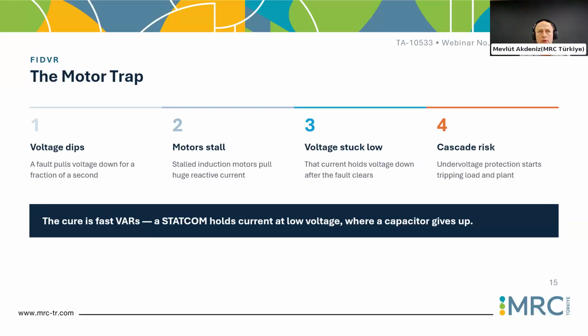And it is also related to the voltage strength of the grid at that point that I mentioned a couple of minutes ago. The voltage strength here is not only the short circuit power, but also the QV curve edge points. Because even if we have short circuit power here, maybe from huge power plants, if the short-time overloading of the reactive power of the system is not high enough, short circuit power alone does not guarantee recovery from such dynamic or slow voltage recovery issues in the grid. So we need both short circuit power strength and fast reactive reserve at these problematic areas dominated by motor load and connected to long lines.